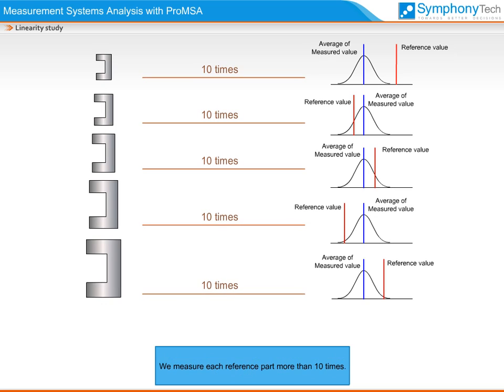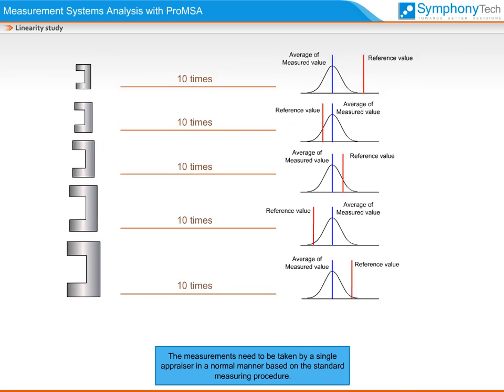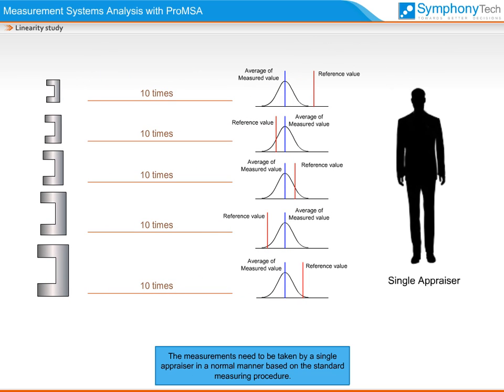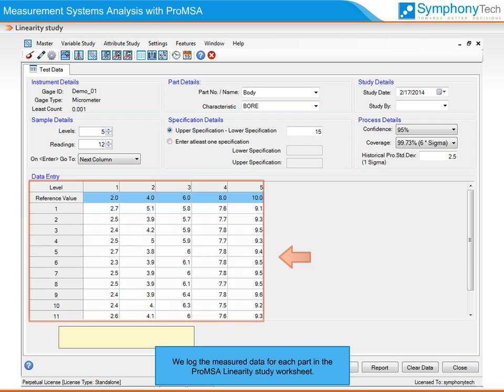We measure each reference part more than 10 times. The measurements need to be taken by a single appraiser in a normal manner based on the standard measuring procedure. We log the measured data for each part in the Pro-MSA linearity study worksheet.